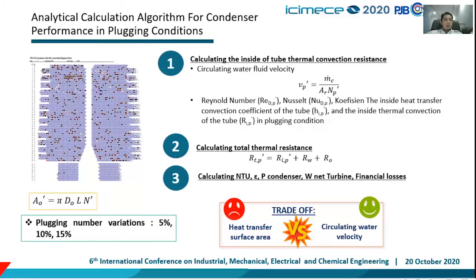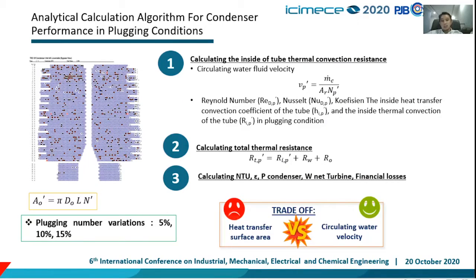Here is the analytical calculation algorithm for condenser performance in plugging conditions. We use three plugging number variations: 5%, 10%, and 15%. On one hand, plugging conditions will reduce the heat transfer surface area, but on the other hand, plugging will increase circulating water velocity, which is beneficial for heat transfer. So we will study which effect is more significant to condenser performance.